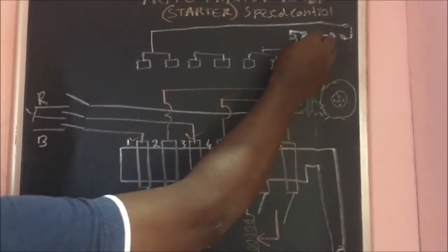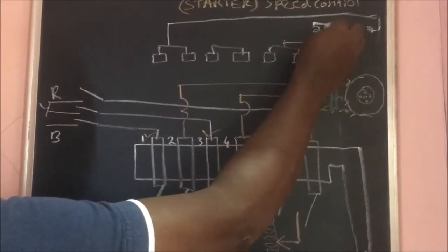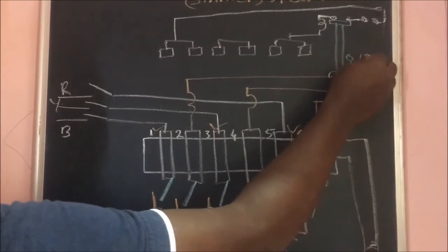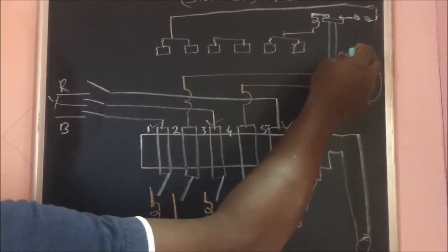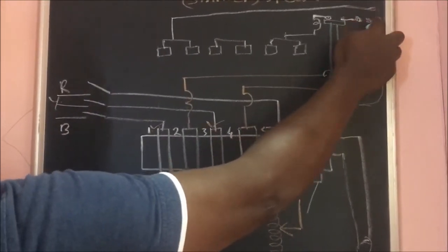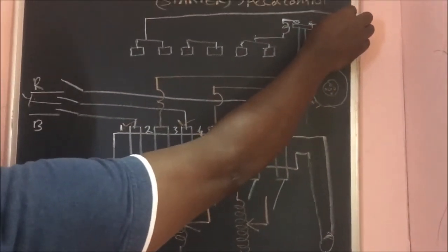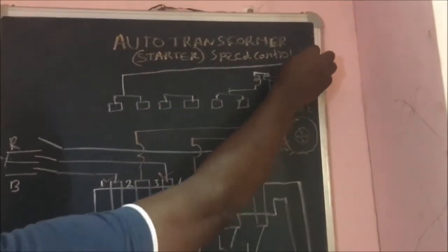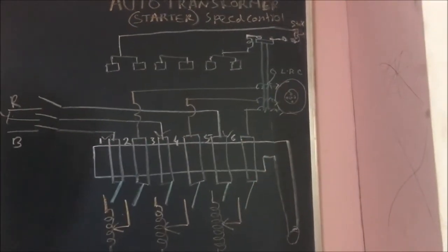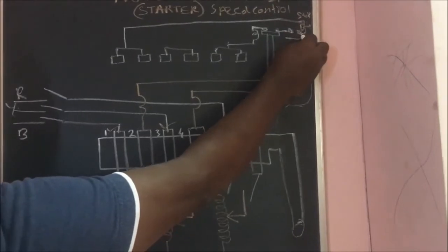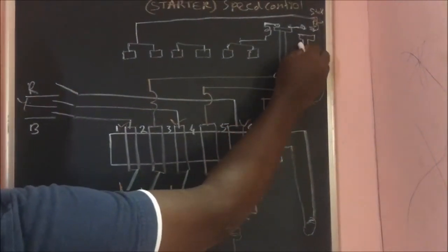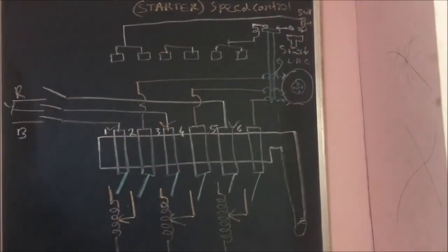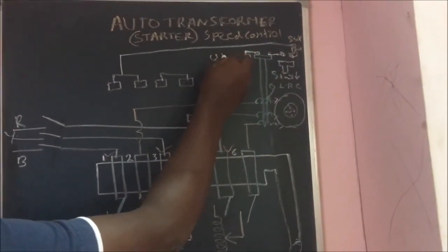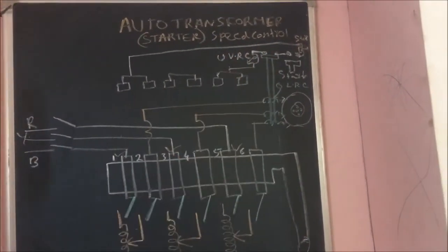Actually in the original construction 1 2 3 4 5 6 are in the core only. It will not go up, it is internally connected, but we are making it on top only for diagram simplification. Then you have to take outputs from 2 4 6. It goes to the three-phase squirrel cage induction motor. Therefore you have to make a symbol of a squirrel cage rotor.